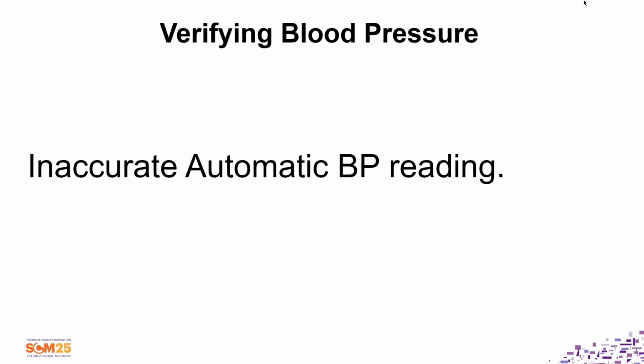Okay, verifying blood pressure. How many times have you questioned your automatic blood pressure? Many times. What do you do? You go get a manual, right? And then put the manual on. Know that actually there's an instruction for use in one of the older manuals to verify blood pressure. If you have a question, you put on the cuff, initiate the blood pressure, and take a stethoscope. Use the stethoscope, and while the machine is decaying in its pressure, watch the pressure on the machine because that is accurate.